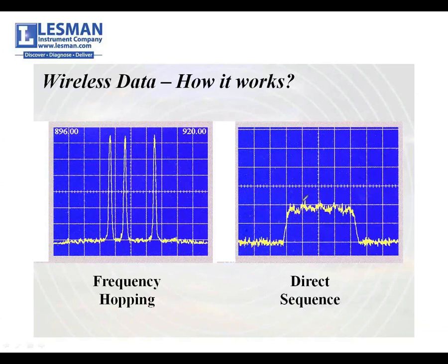When you go to the higher frequencies of 2.4 gigahertz and 5.8 gigahertz, and you shift over to the direct sequence strategy, you get a much broader shot, meaning you're moving a lot of data. So now we're talking about Ethernet, maybe camera feeds, maybe huge amounts of I/O. We can move a tremendous amount of data, but we can't shoot it as far because it doesn't have the power behind the shot. And we can't get through as many walls, or it has reduced boring power. So hopefully that's apparent. A lot of boring power, not so much boring power. A little bit of data, lots of area for data during the communication sequence.